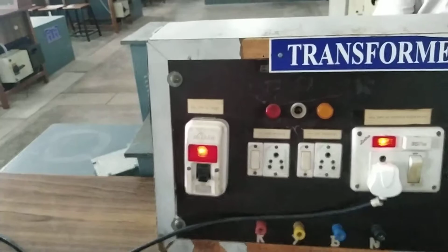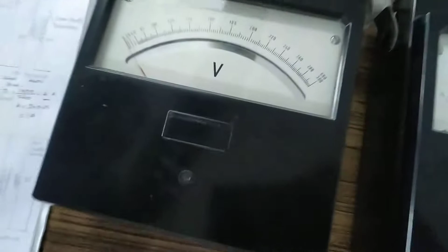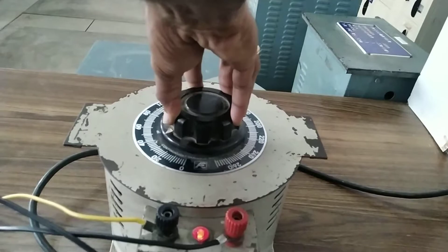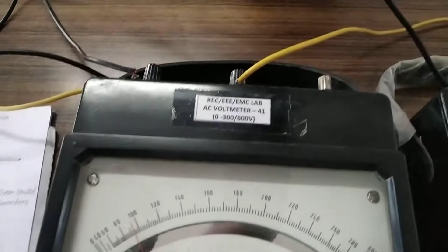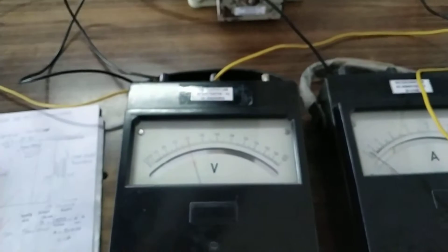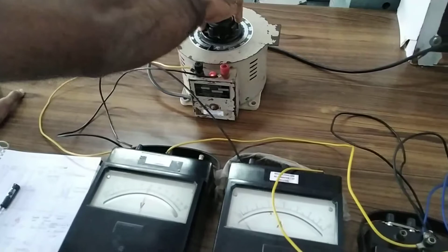Now you have to give a supply voltage, the rated voltage, to the transformer. By observing the voltmeter and varying the auto transformer, you can provide the rated voltage to the transformer. You can see the voltage increasing as you increase the auto transformer setting. So now you have to make the voltage exactly 240 volts.